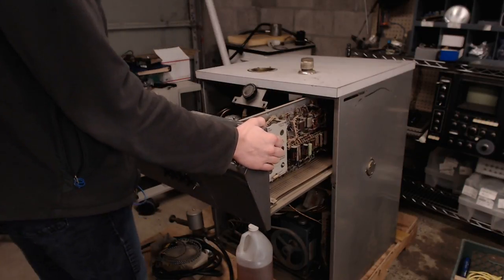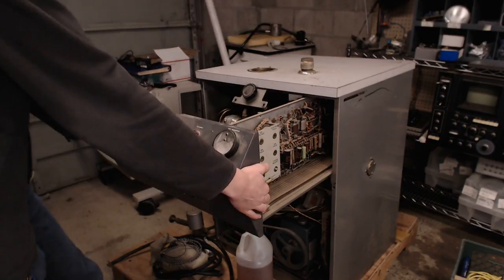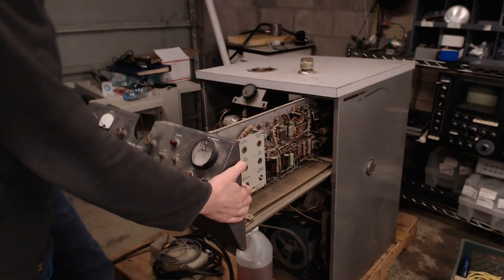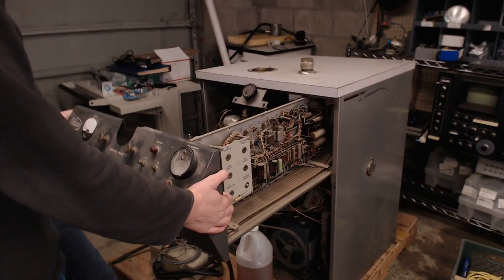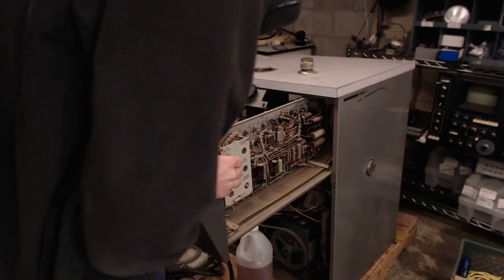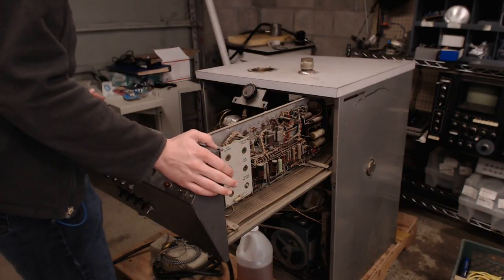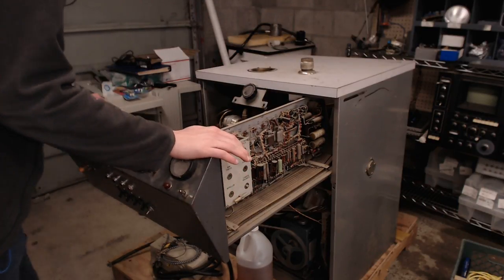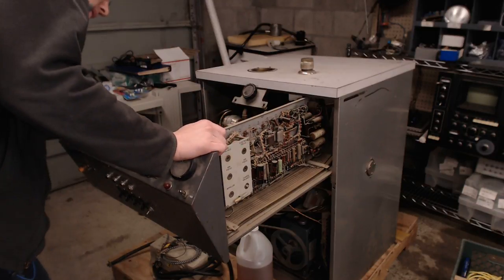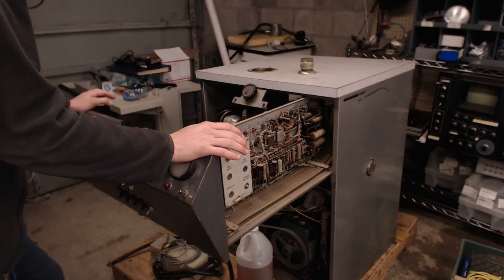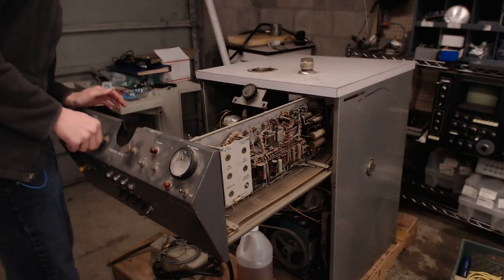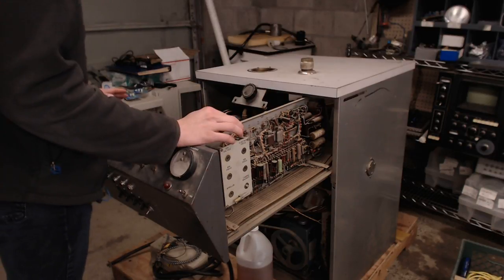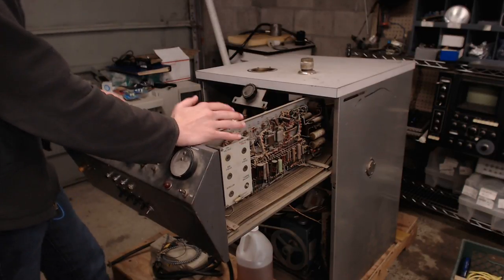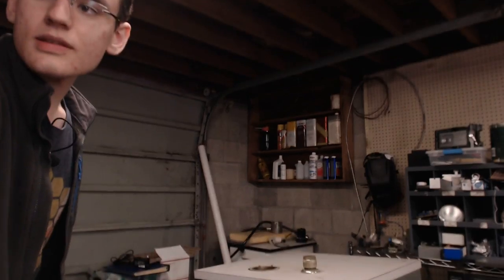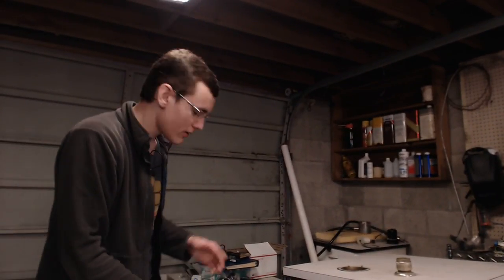So the way one of these things works is that you're working with high vacuum, even things like ultra high vacuum, where even regular O-rings still leak enough to cause you problems because you're trying to get so many air molecules out. An O-ring can't stop leaking, so you have to use metal on metal seals and knife edges, and it gets kind of crazy. But one of the ways you can find leaks is that helium is relatively small and relatively rare in our atmosphere.